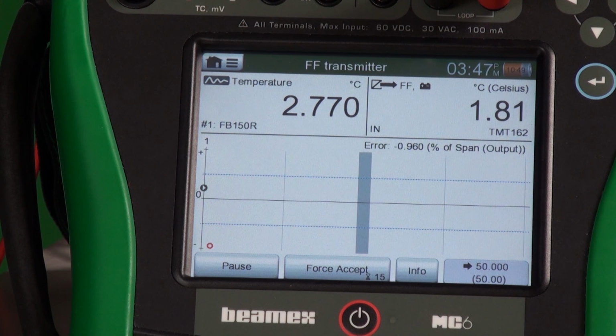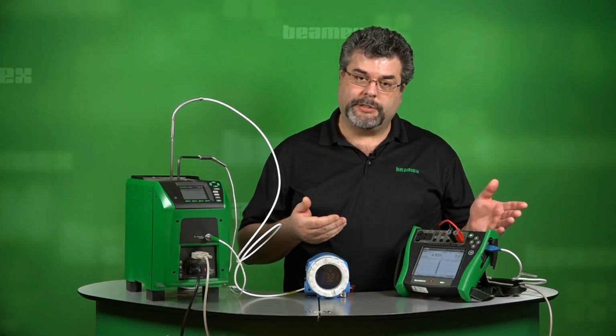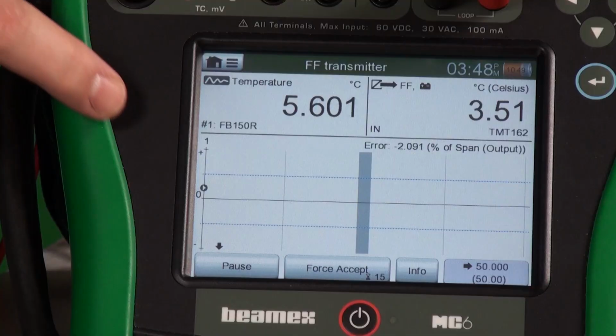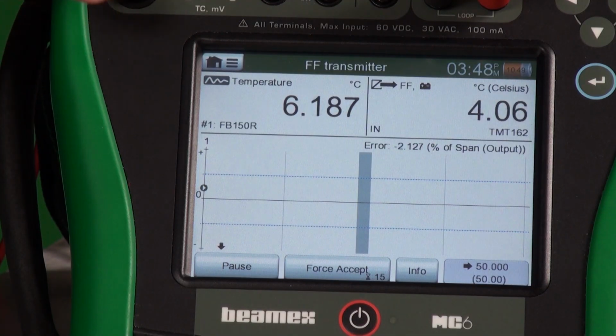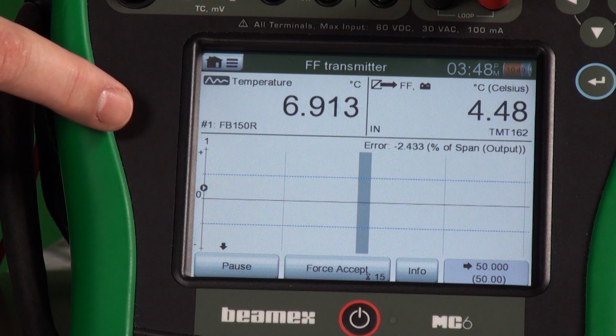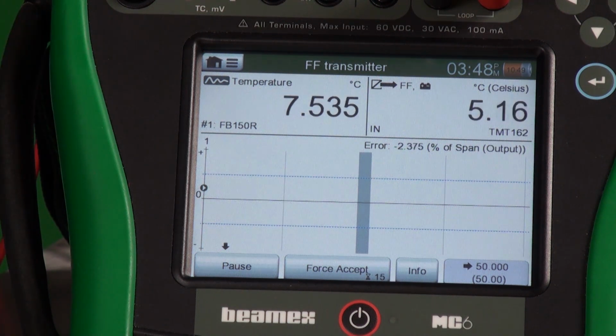With the graph, this middle point is our 0. So if our dots line up along the 0, we have no error. We have a predefined error tolerance, and that is signified by the blue dashed lines. We have an error tolerance set up of 0.5% of span.